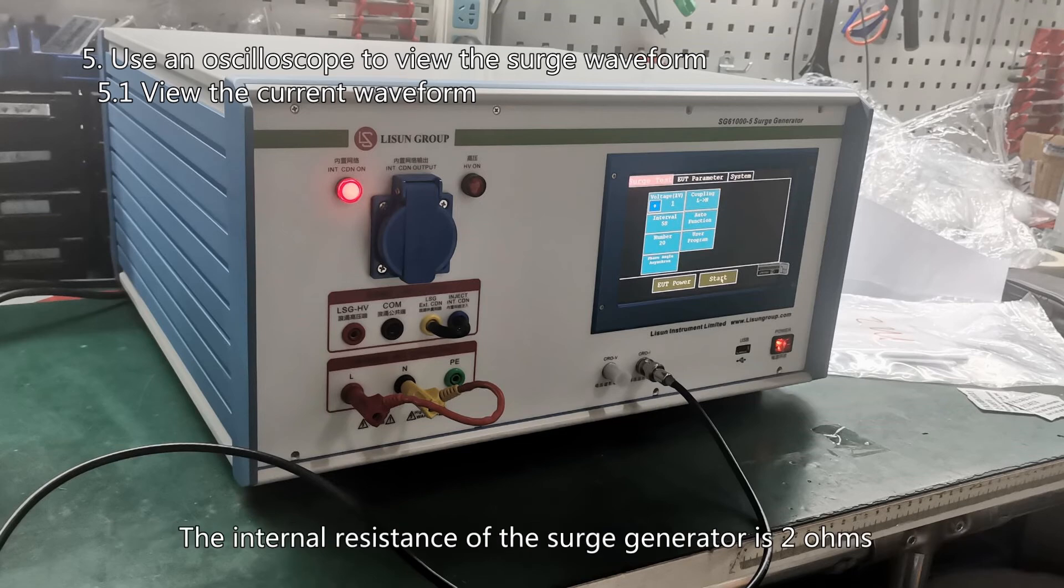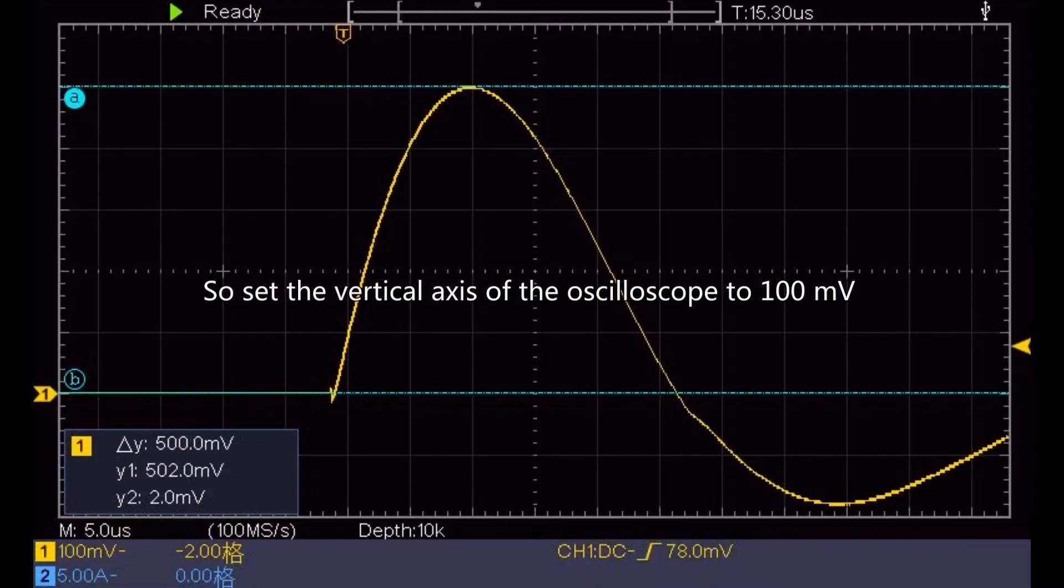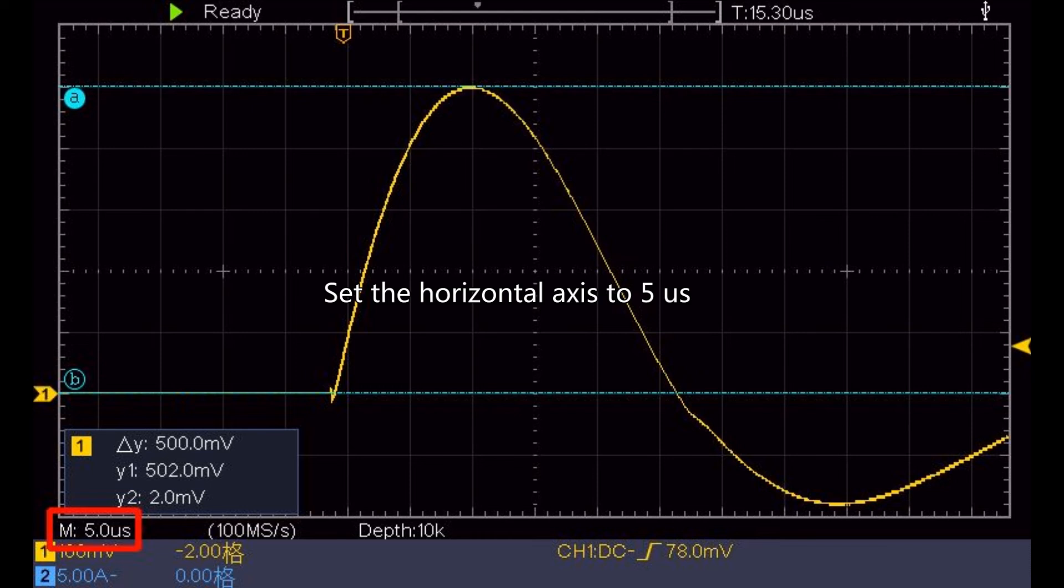The internal resistance of the surge generator is 2 ohms. So set the vertical axis of the oscilloscope to 100 millivolts. Set the horizontal axis to 5 microseconds. Other parameter settings are the same as when viewing the voltage waveform.